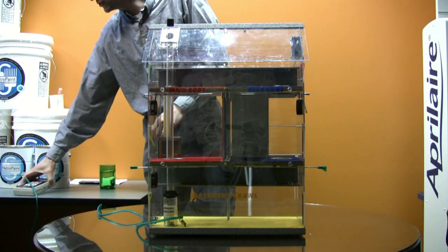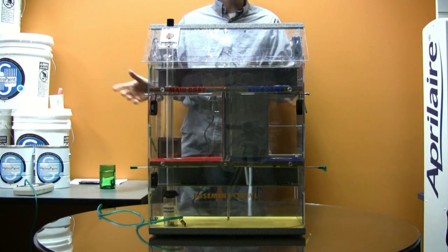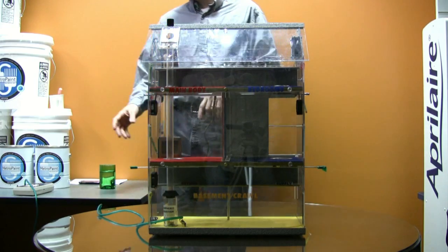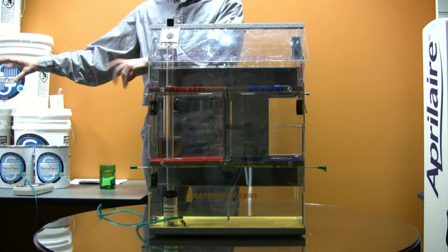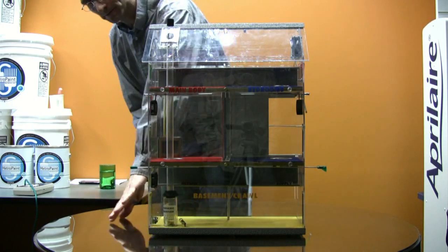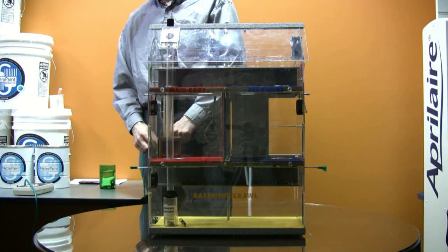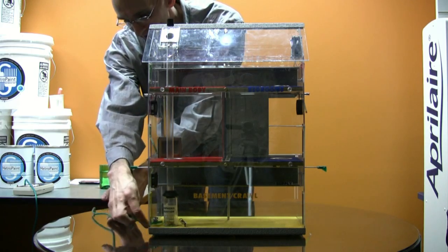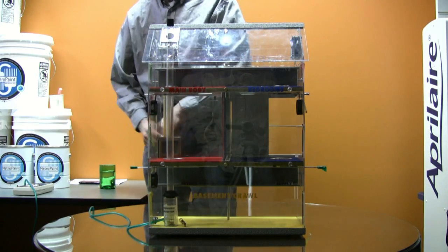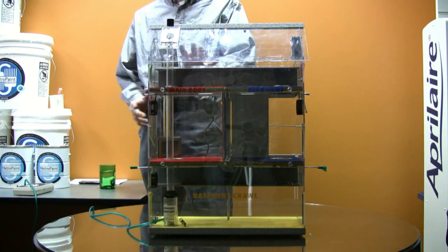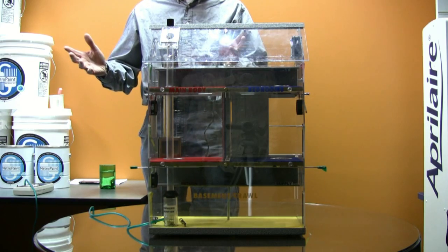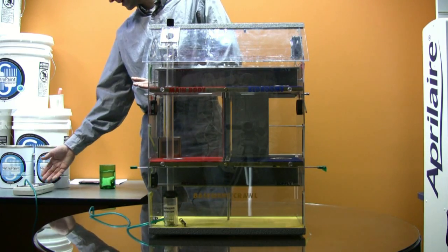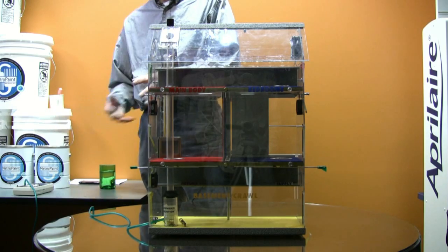So when you do building diagnostics, say for a house, initially you set up what is the pressure differential with respect to the outside. So we have a combustion zone right here. What is the pressure differential between that combustion zone and outside? Well, it ought to be 0 right now because this is a toy house set up inside this building. We really ought not to have a difference there. And our manometer says the difference is 0.